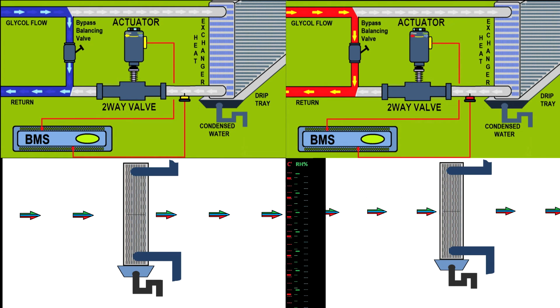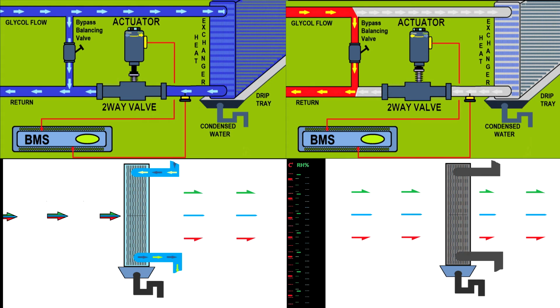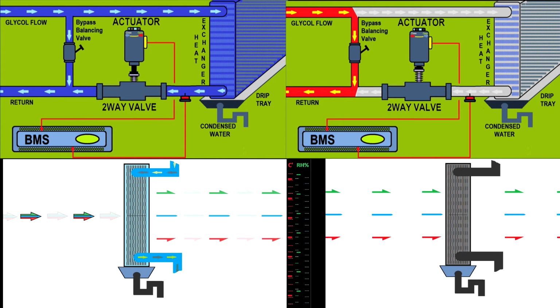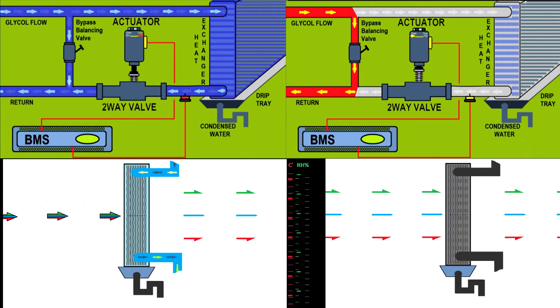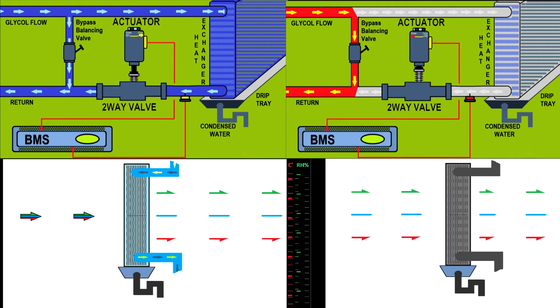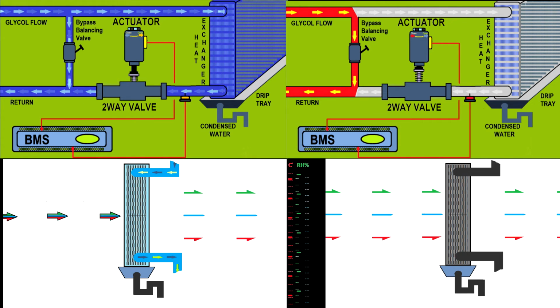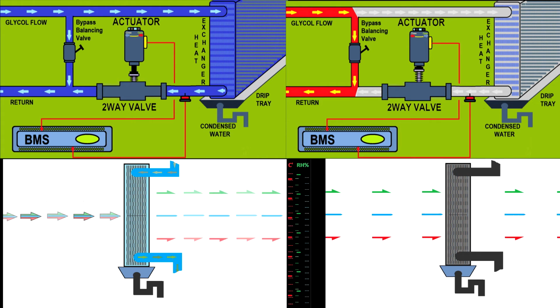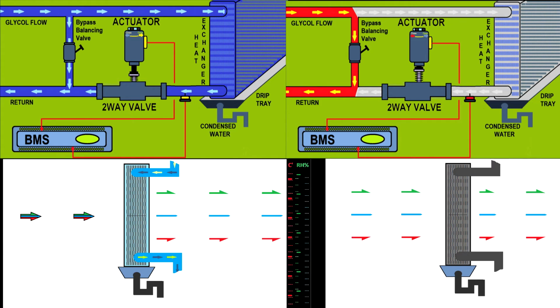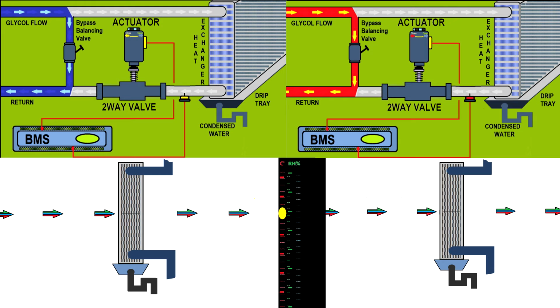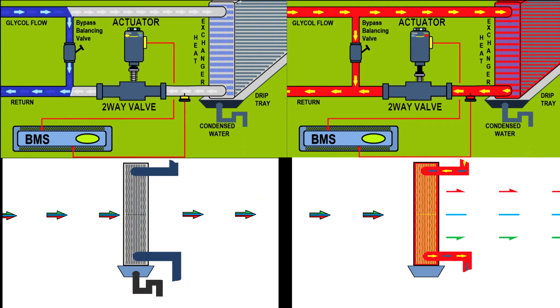Now you have to see how the air is acting when the heat exchanger is running. As you see, the air is going through changes, like it's got humidity, and in this case you'll see the absolute humidity is the blue line in the middle, it stays. The relative humidity is green, goes up, and the temperature is red, goes down. So we do not remove moisture from the system. If the heat exchanger is turned off, then obviously no cooling, the air comes back to its original status.